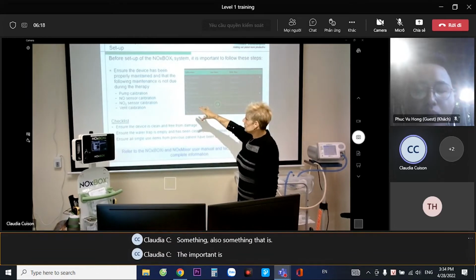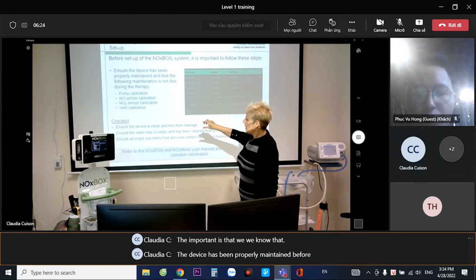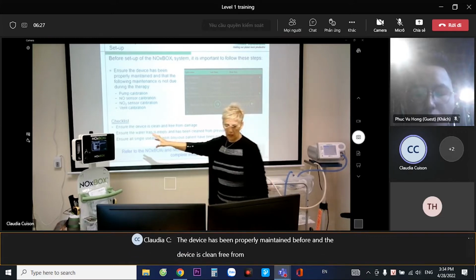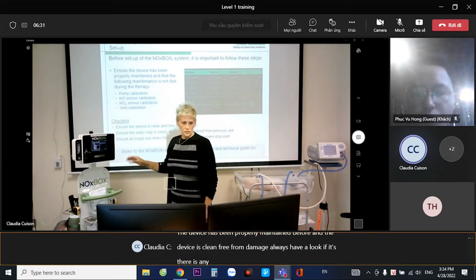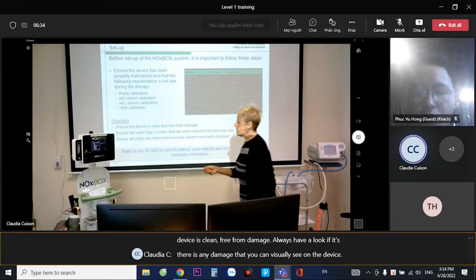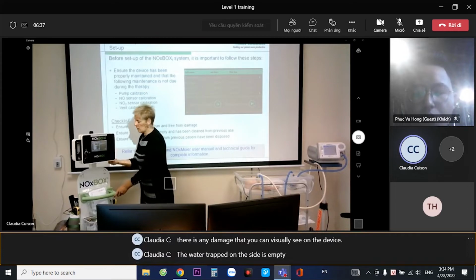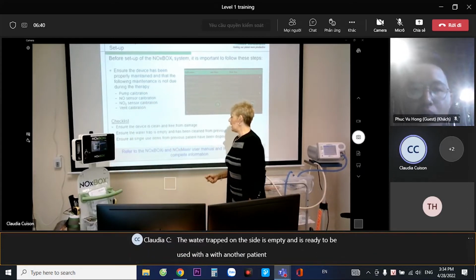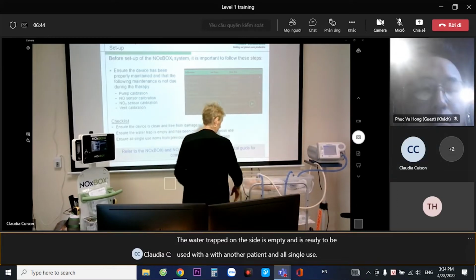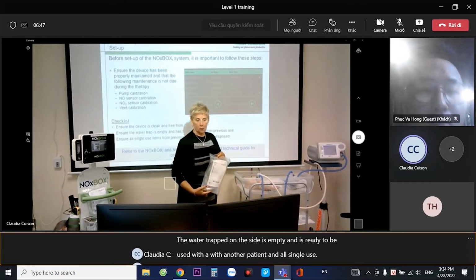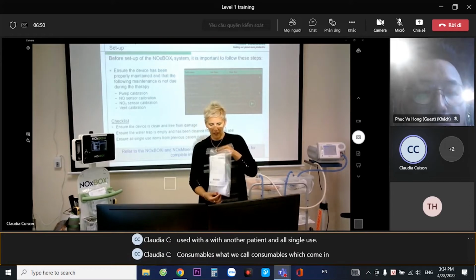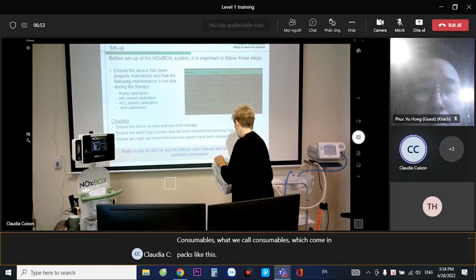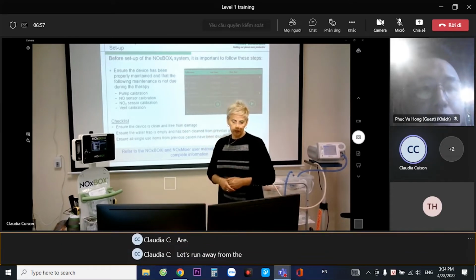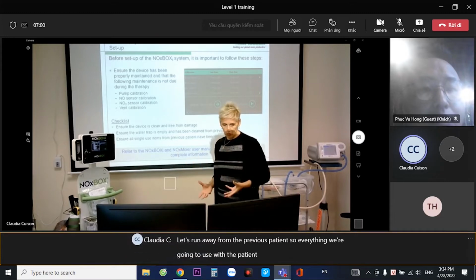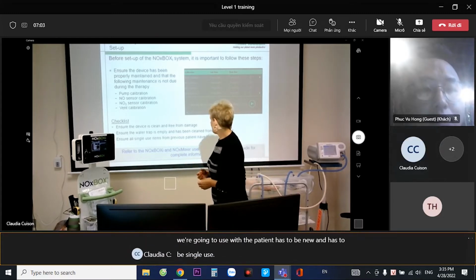Something that is important is that we know the device has been properly maintained before, and the device is clean and free from damage. Always have a look to see if there is any damage that you can visually see on the device. The water trap on the side is empty and is ready to be used with another patient. And all single-use consumables, which come in packs like this, are thrown away from the previous patient. So everything we are going to use with the patient has to be new and single use.